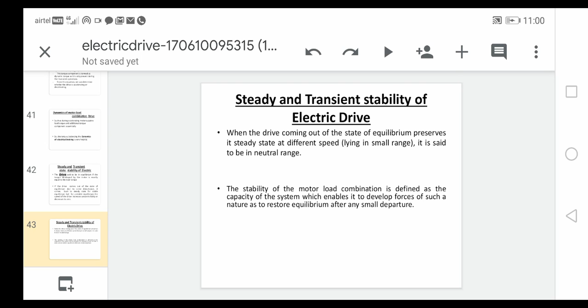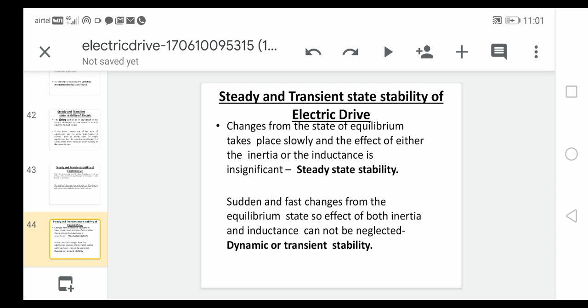The stability of the motor load combination is defined as the capacity of the system which enables it to develop forces to restore equilibrium after any small departure. Steady and transient stability of electric drive. Changes from the state of equilibrium that take place slowly, where the effect of either the inertia or the inductance is insignificant, we call steady state stability. Sudden and fast changes from the equilibrium state, where the effect of both inertia and inductance cannot be neglected, we call dynamic or transient stability.